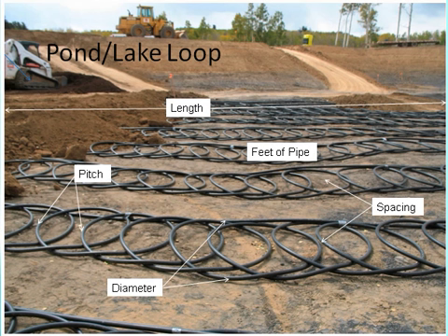Typical pitches are going to be 18 to 24 inches. I've seen sometimes as little as 12 inches, but that's pretty tight. And then the diameter, it's what is the diameter of the pipe as it's being coiled. And again, typically it's 2 feet or 3 feet. And then the spacing is the center from one coil to the center of the next coil.